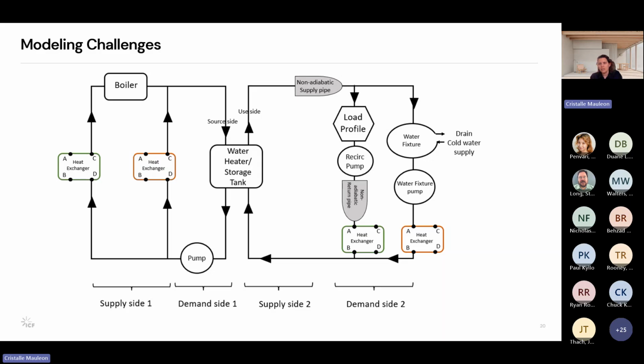However, what we found is that heat exchangers behave as active components, which means they override flow dynamics rather than passively transfer heat. We tried using energy management system controls, but we were unable to balance the flow rates on both sides of the heat exchangers, which led to unstable and unrealistic simulation behavior. As a result, we had to remove the heat exchangers and simplify the architectures to maintain the model stability and ensure we were getting results that made sense. This limitation underscores the need for improved flow control capabilities in EnergyPlus when complex domestic hot water systems, which have interacting loops, are modeled.